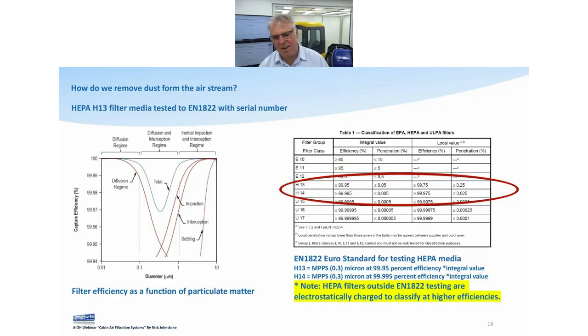H14 is 99.995% efficient at 0.3 of a micron. On the table, the diameter of particle size ranges from 0.1 to 1 micron, and somewhere in that 0.2 to 0.7 range — with 0.3 sitting in the middle — those are the hardest ones to catch. Below 0.1 micron they actually start getting easier to catch again. The key thing I highlight is that as that filter does its job and airflow is kept as low as possible, it becomes even more efficient.